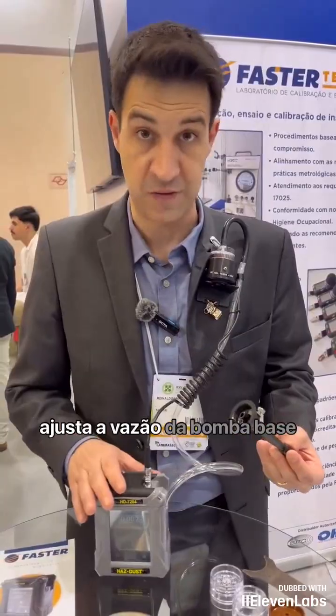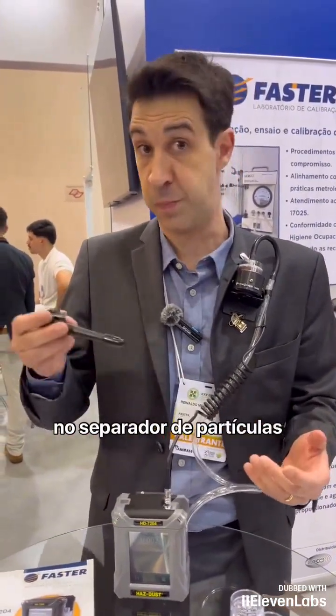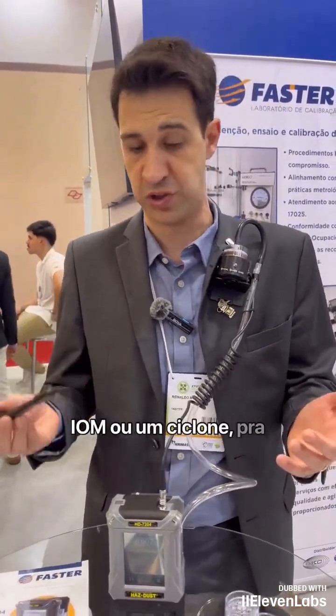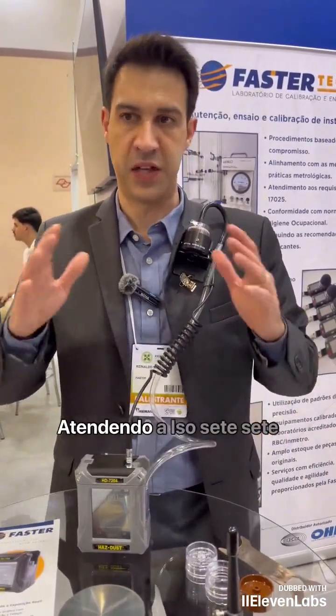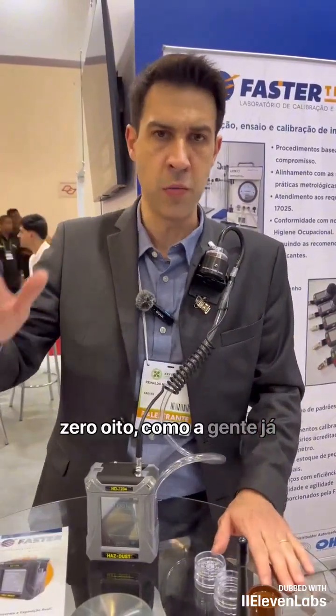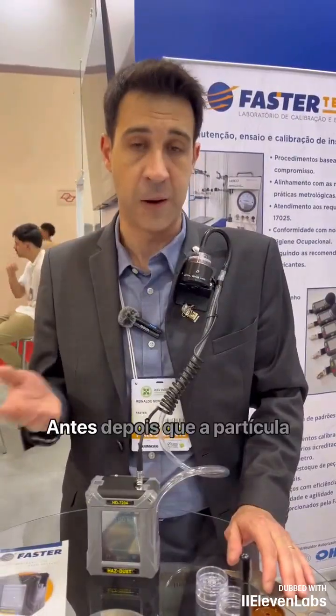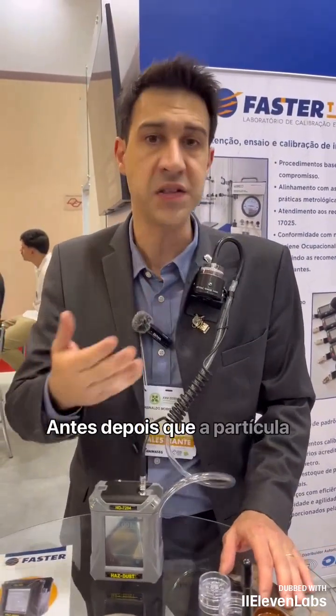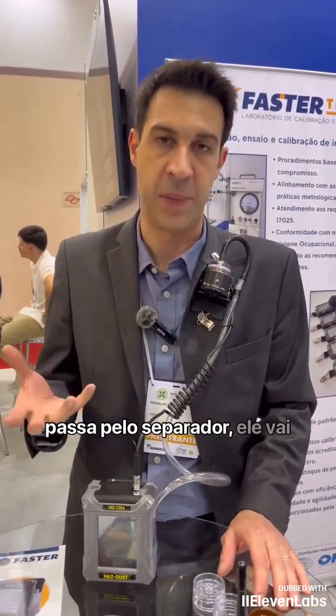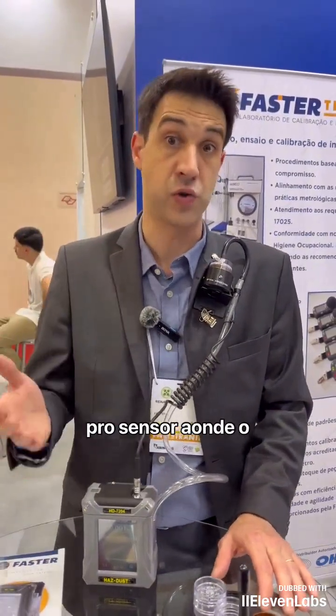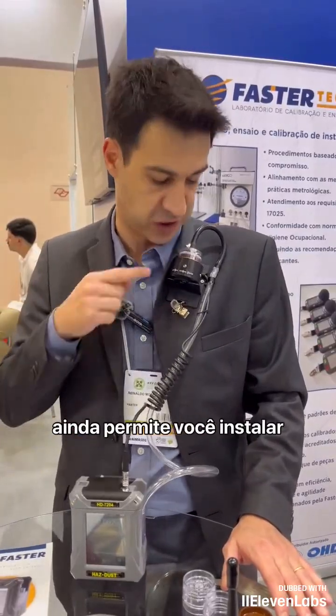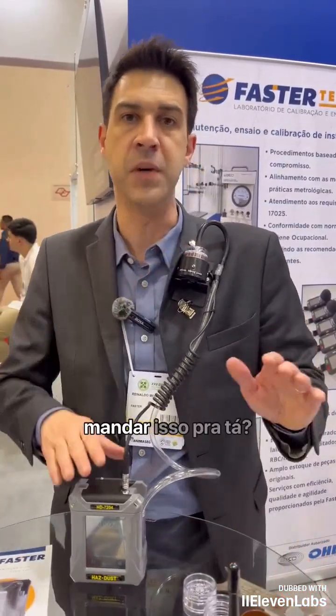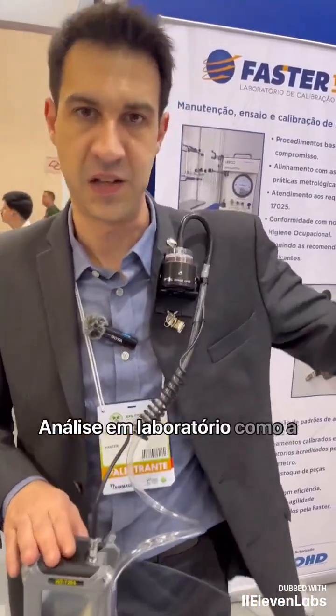You adjust the pump flow rate based on the particle separator you're using, whether it's an IOM or a cyclone, to physically separate the particles, complying with ISO 7708, as we already do today with conventional pumps. What's the only difference? After the particle passes through the separator, it goes to the sensor where the device measures the concentration of the particulate, and in the end, it still allows you to install a conventional cassette and send it for analysis. But laboratory analysis, as we already use.